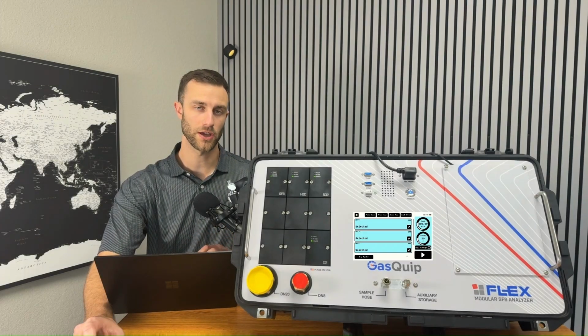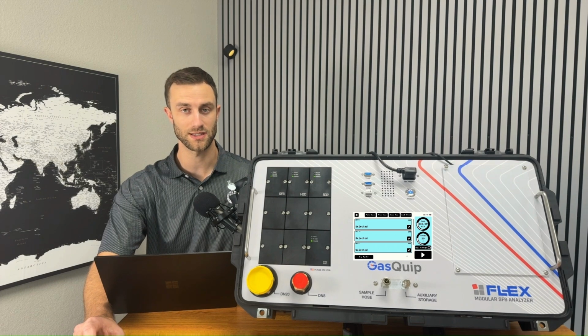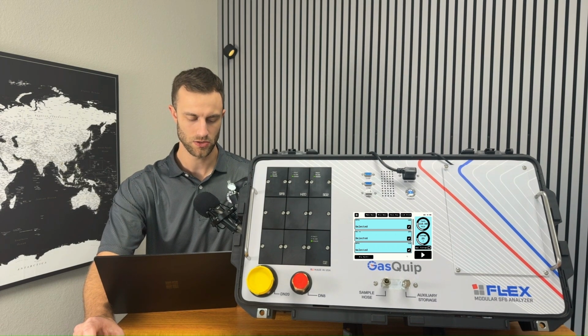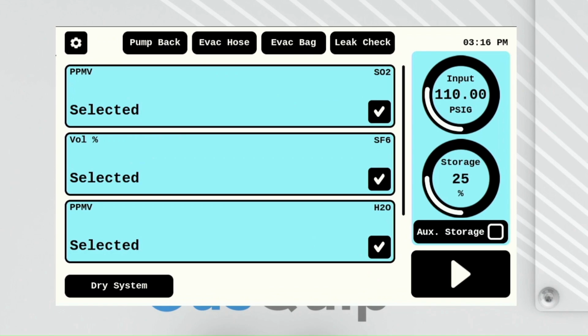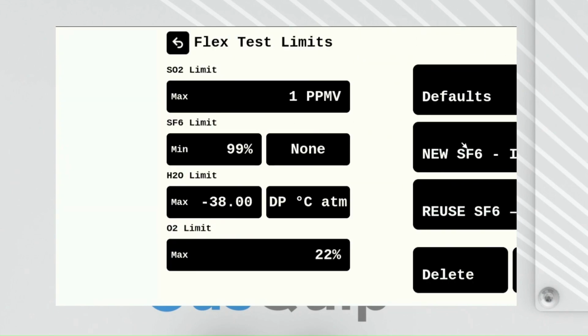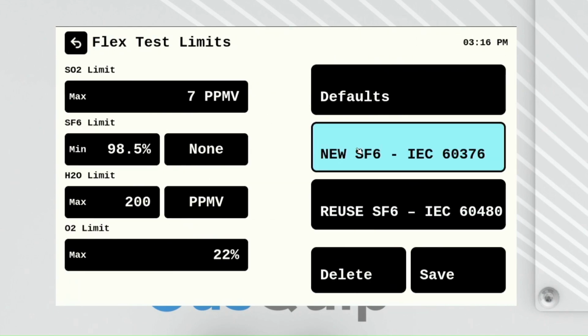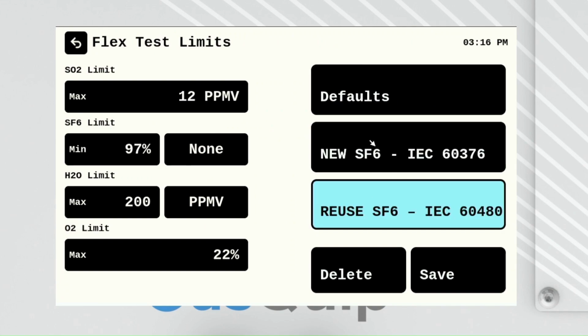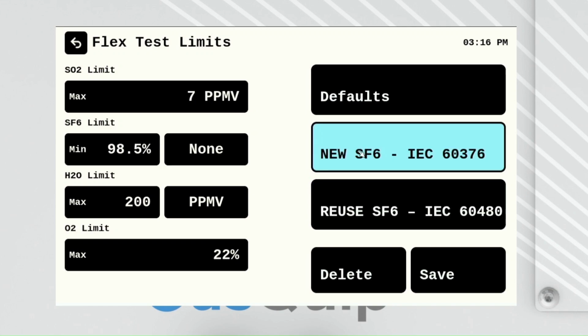We will touch on this later, but I want to show you right now what it looks like to use the test limits inside our Flex analyzer. So let's go to the close-up view. If you go to settings and then go to test limits, we have preloaded the different IEC recommendations for new and reuse SF6 that we just covered. So you can easily click those and it'll apply to the test that you run.